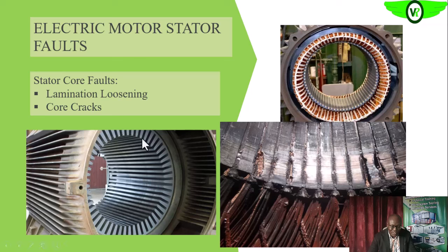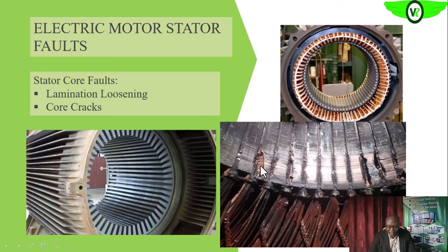The stator itself can also have physical faults. This is the yoke of the stator, which is the main structural part where the winding sits. As you can see, this is a clear case of rubbing of the rotor on the stator — the yoke has been damaged, and the winding is already shorted to either the rotor or the yoke.